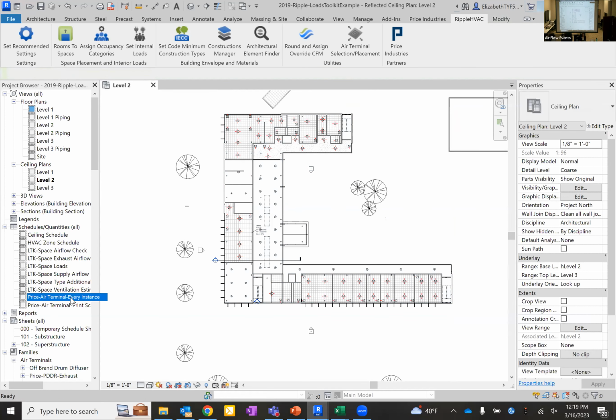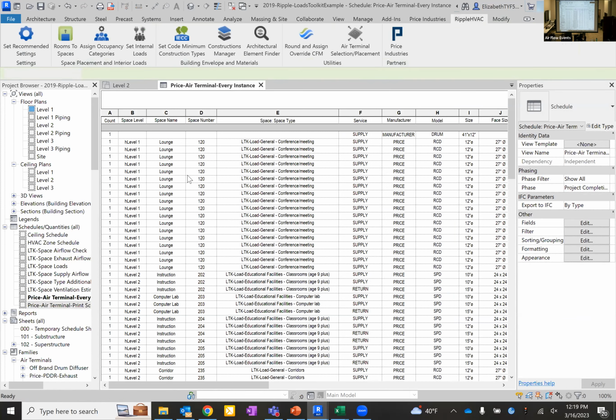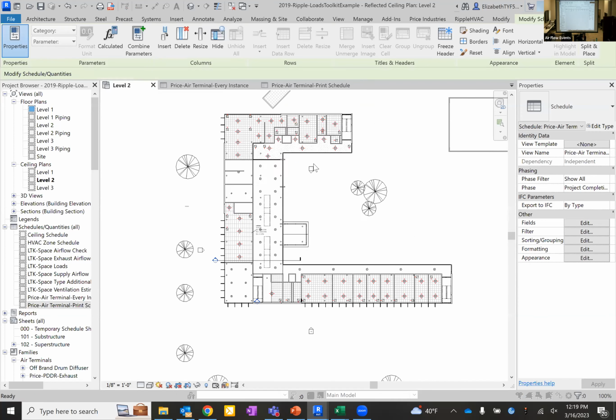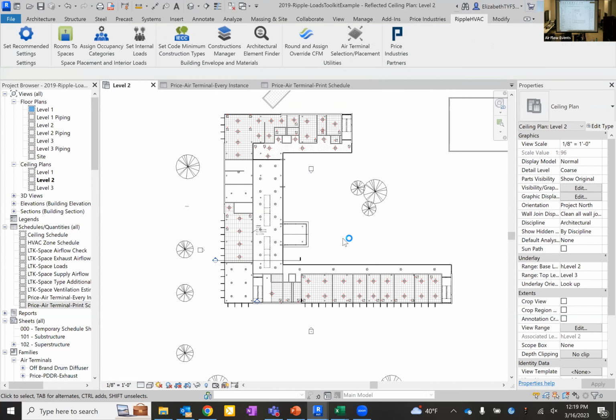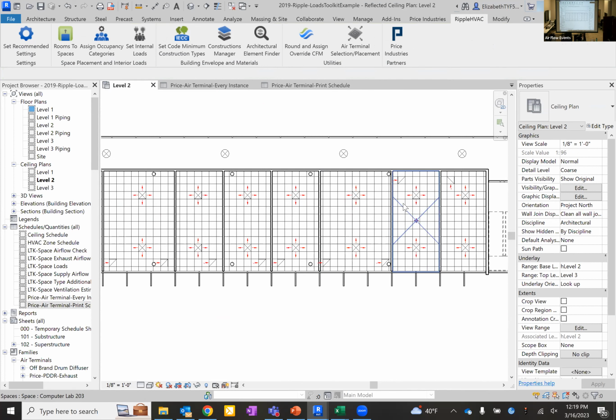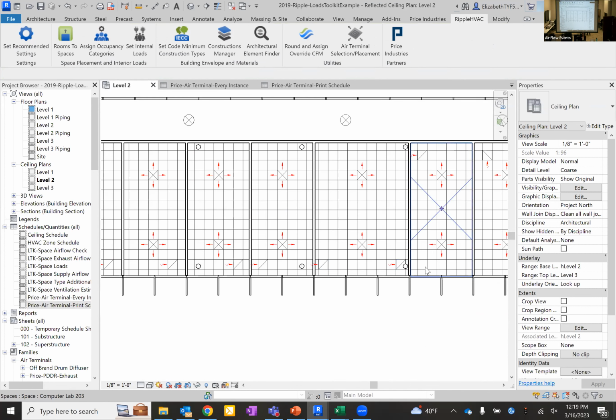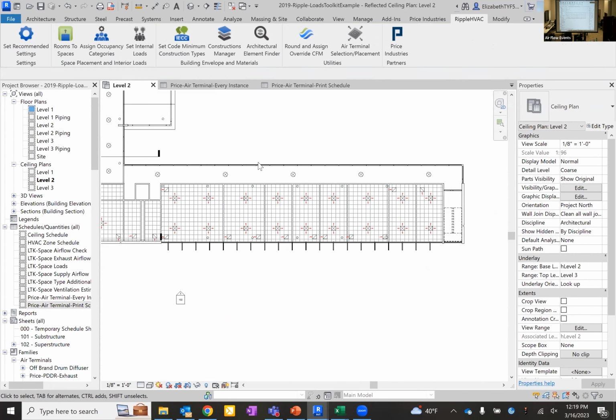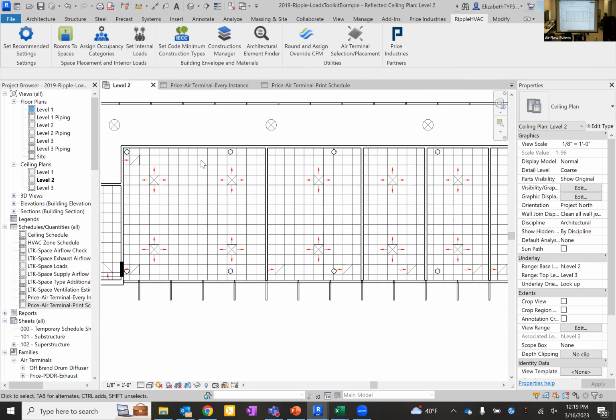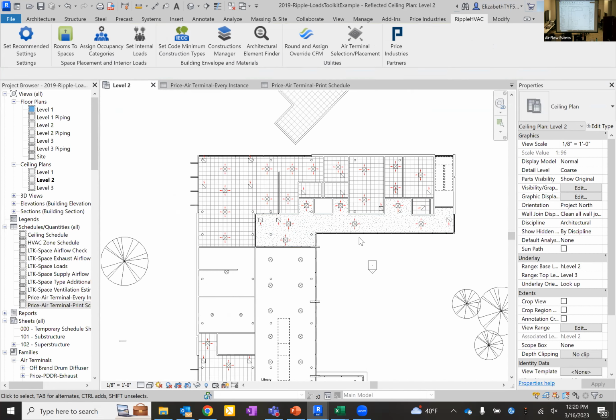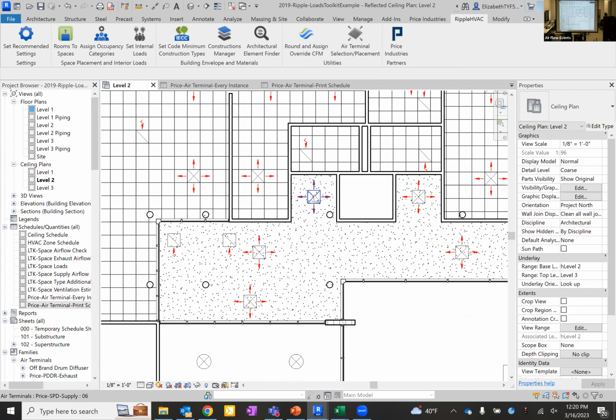We have, I believe, 128 diffusers placed. Okay. Now if I zoom into some of these rooms, you can see for the supply diffusers, it's trying to pick the best location, usually in the center of the room, either right in the middle or staggered pretty normally throughout the space. It's always going to try to put the return in the corner of the room. Now for a square room like this, it does pretty well. We've got a square plaque in each corner there. But you might look at some of these other spaces and think, what is it doing? Why is it putting a diffuser in that little alcove? That may or may not be how you design it.